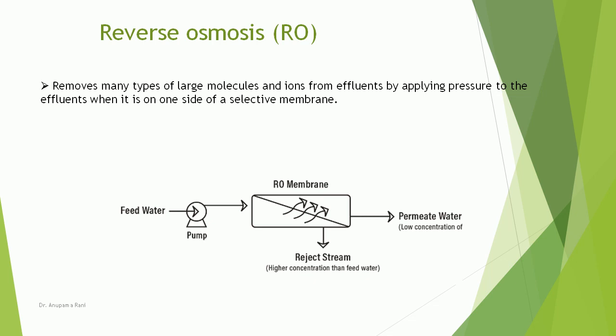The demineralization of water can be accomplished using thin, microporous membranes. There are two basic modes of operation in use. One system uses pressure to drive water through the membrane against the force of osmotic pressure and is called RO. The pressure applied is several orders of magnitude in excess of natural osmotic pressure. The membrane commonly used in reverse osmosis is composed of cellulose acetate and is about 100 micrometers thick.